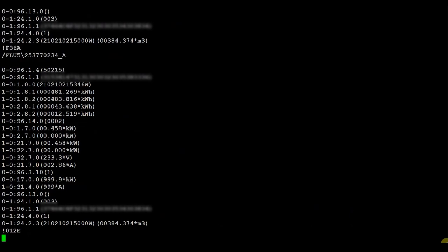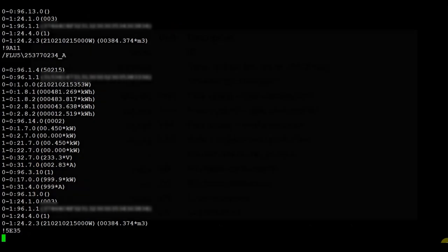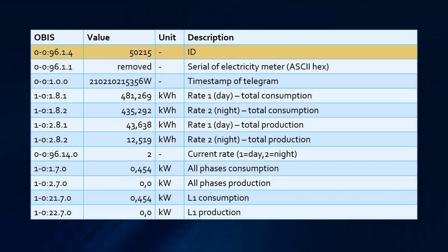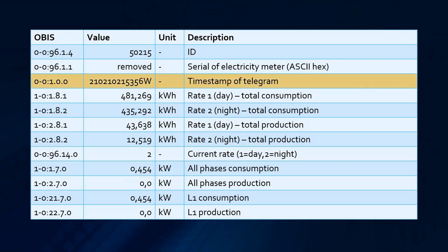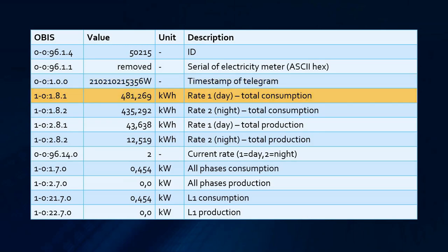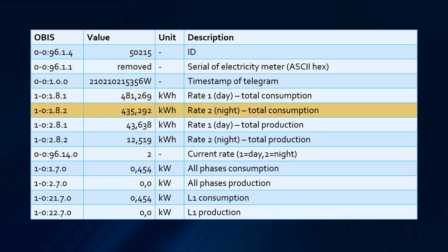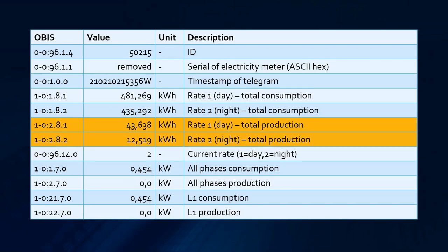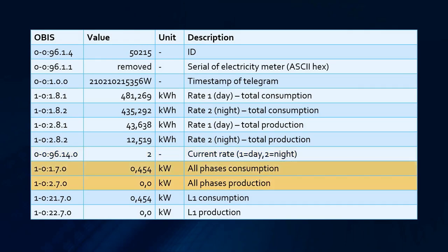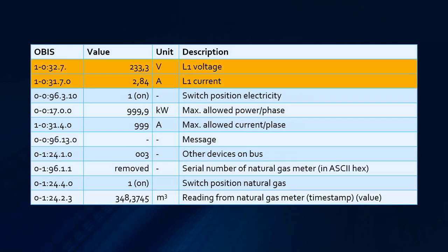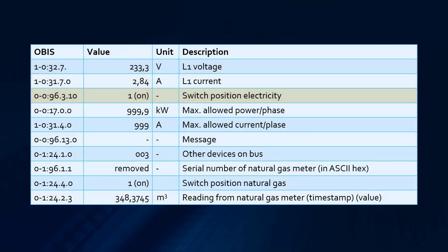Now we are ready to read data from the serial port. As you can see, this looks exactly as what I described before. Let's take a single message from the output and try to map it to the OBIS codes. First we have the ID followed by the serial number of the electricity meter in ASCII hex. Next we have the timestamp of the telegram, then we can see the counter for total consumption during daytime followed by the same for nighttime, and the same for production daytime and nighttime, and which rate is currently active. The next items show current production and current consumption, followed by detail per phase. We can also see the current voltage and current flowing through the meter, and whether the meter is switched on or off.